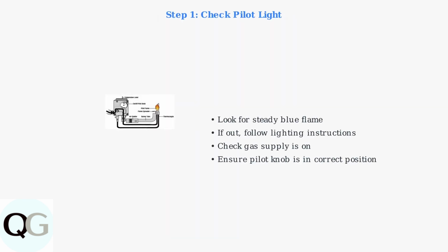Step 1. Check the pilot light. This is the most common issue and often the easiest to fix. The pilot light should have a steady blue flame. Step 2. Inspect the thermopile and wiring connections. The thermopile generates electricity from the pilot flame to power the gas control valve. Check for loose connections and ensure it's clean.